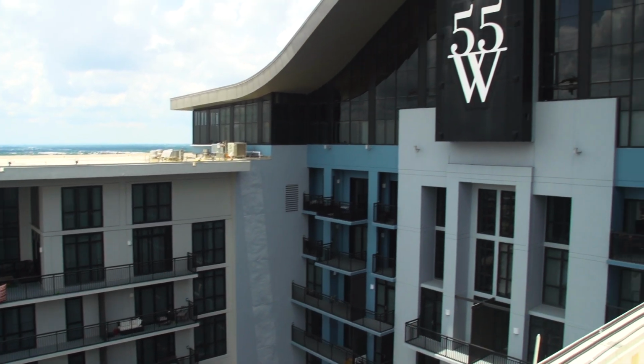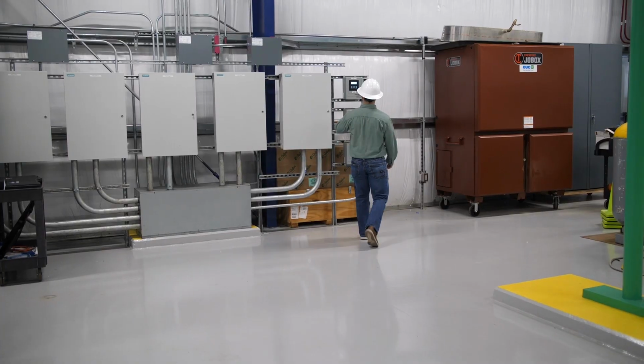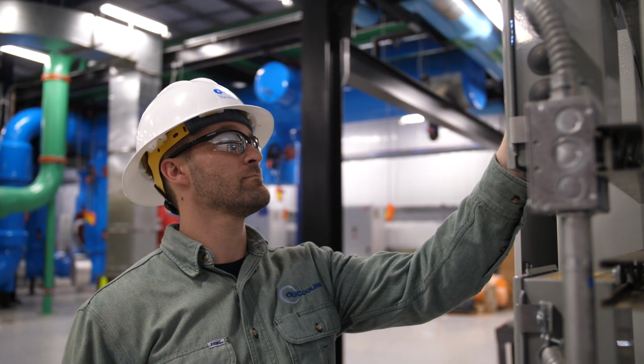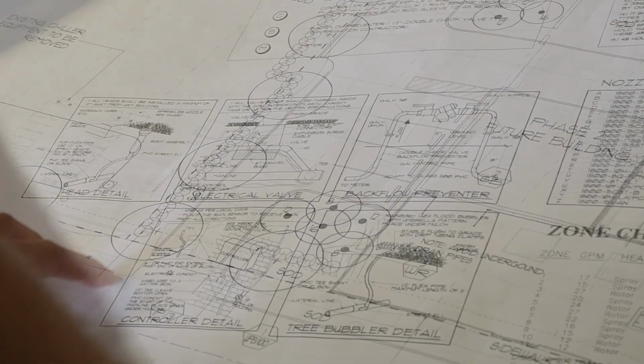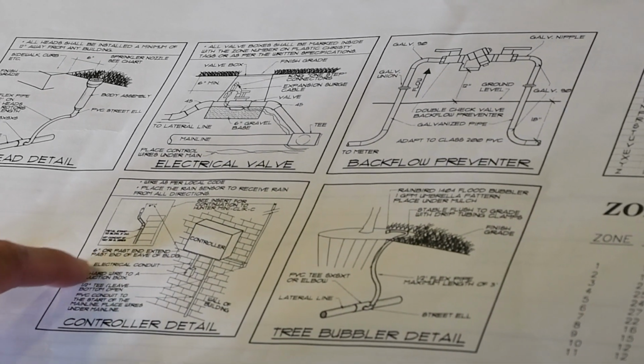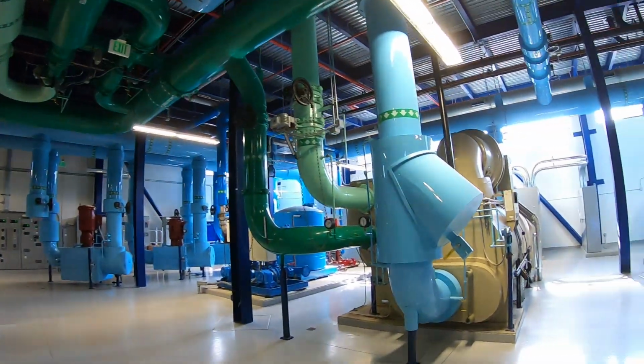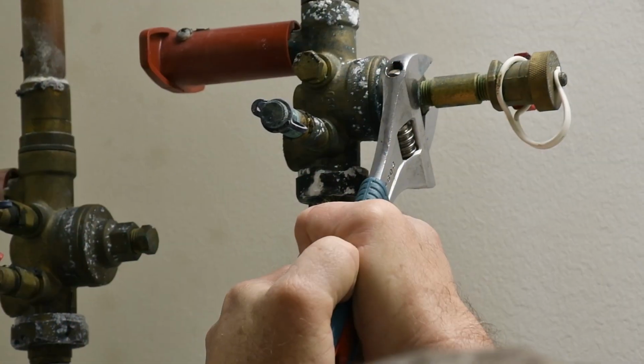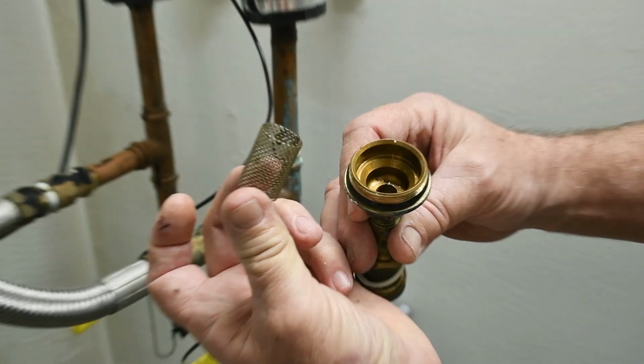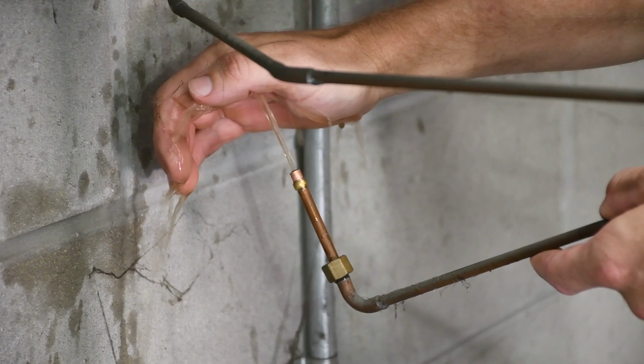It's important to note, the building owner or property manager can request a desired chilled water temperature to achieve maximum efficiency based on the ratings of their equipment. Your building's mechanical drawings contain a list of equipment, including the recommended inflowing chilled water temperature to achieve the proper delta T. Now that you understand the basics of how a chilled water system works, in our next video, we'll explore some of the problems that can lower your building's delta T and increase your costs.